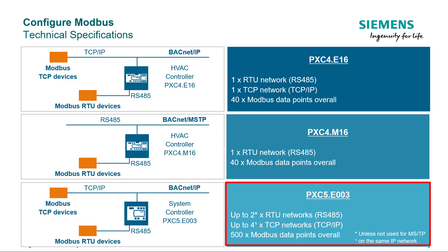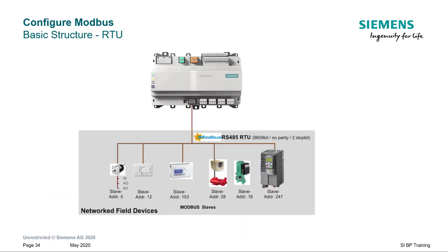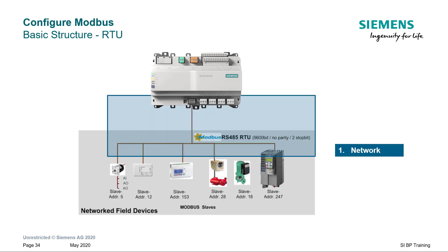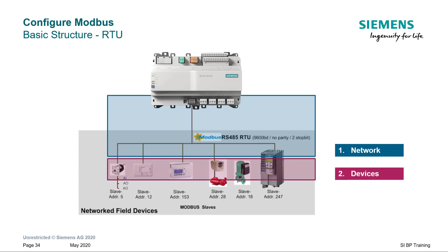The total number of Modbus data points supported is 500. For RTU devices, first it is required to set up a Modbus RTU network. Then all the devices can be added to this network, and finally the data points corresponding to each device can be added.